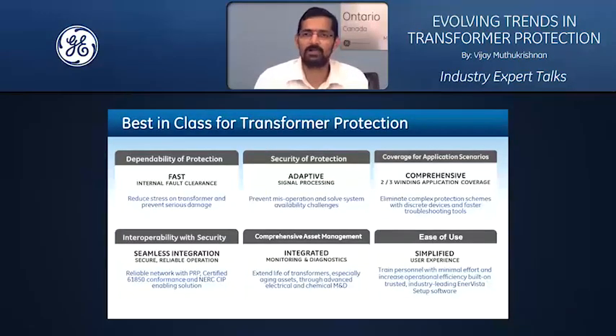The other dimension that has not been touched by the industry to a larger extent is that these transformer protection relays are sitting and watching the transformer 24/7, 365 days, and they really know what's happening in the transformer in terms of monitoring and sensing some of the incipient fault conditions. So can we use this device for enhanced, advanced analytics around asset management, health monitoring of the transformer, or monitoring and diagnostics on a continuous basis? That is the next powerful value you can gain out of your protection relay.